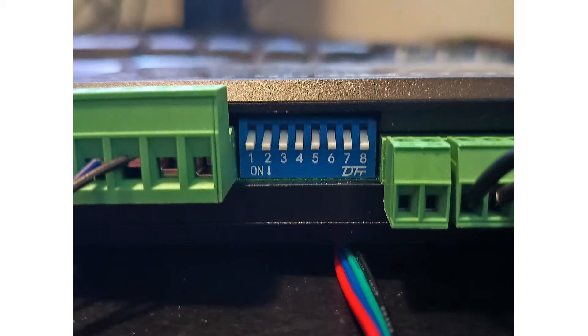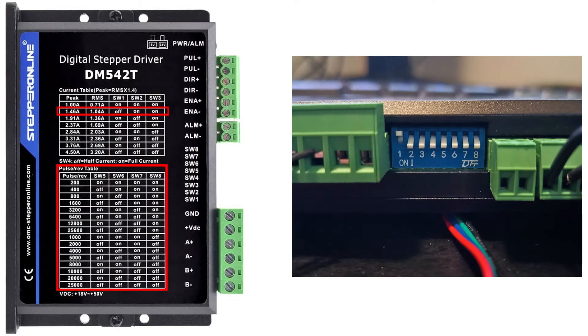On the stepper drive we also have some switches on the side where we can choose the nominal current we want for the motor, and also how many pulses per revolution we want to use. We need to check the manual for the motor and find how much current it needs. My NEMA 17 stepper motor has a nominal current of 1.5 amps, so I will set my first three switches to the closest I can get to 1.5 amps — which is 1.46 amps. I will set switch 1 to off and the rest to on. For the pulses per revolution switches I want 1000 pulses per revolution, so I will set switch 5 to off and leave the rest on.